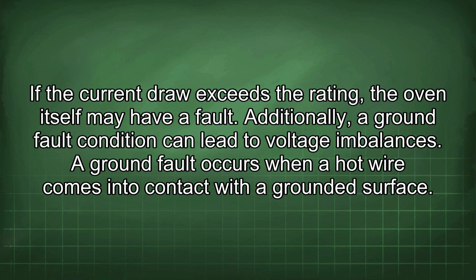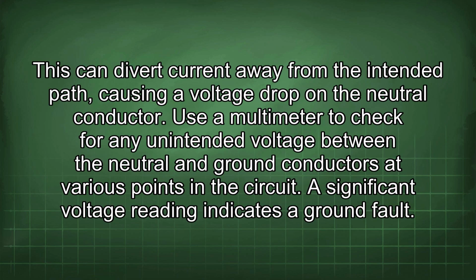Additionally, a ground fault condition can lead to voltage imbalances. A ground fault occurs when a hot wire comes into contact with a grounded surface. This can divert current away from the intended path, causing a voltage drop on the neutral conductor. Use a multimeter to check for any unintended voltage between the neutral and ground conductors at various points in the circuit. A significant voltage reading indicates a ground fault.